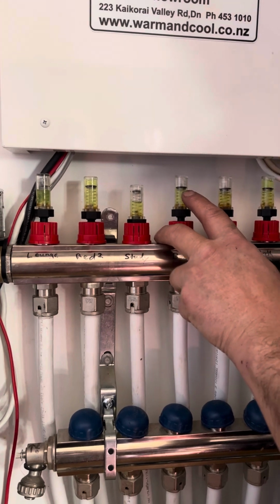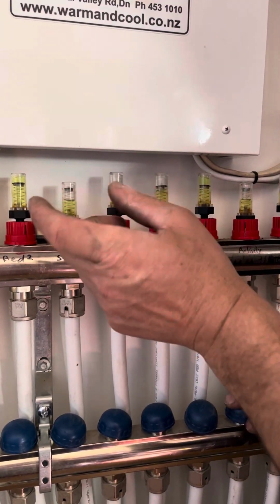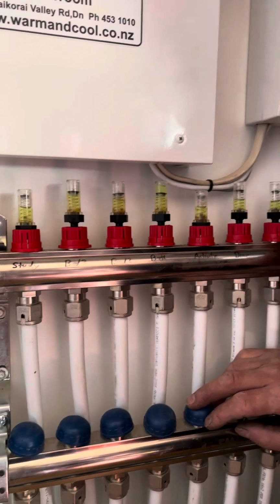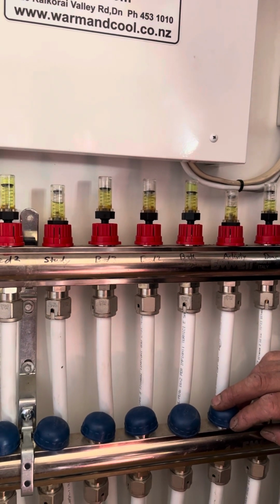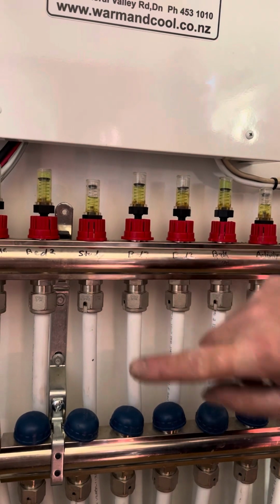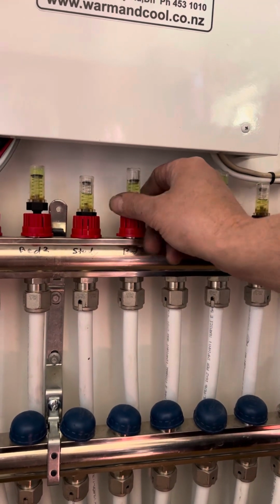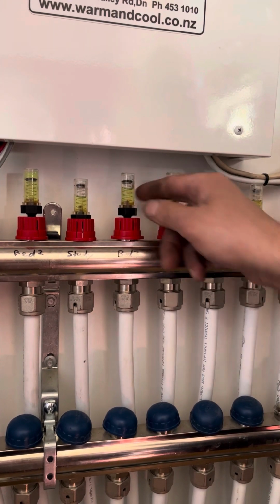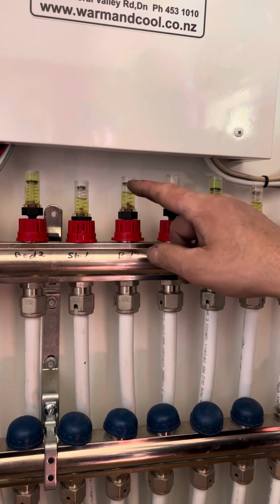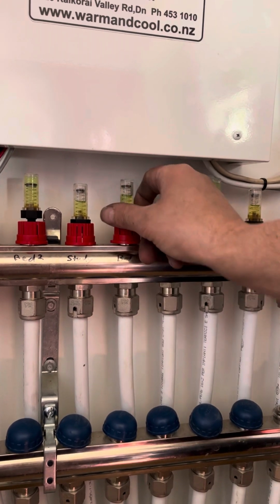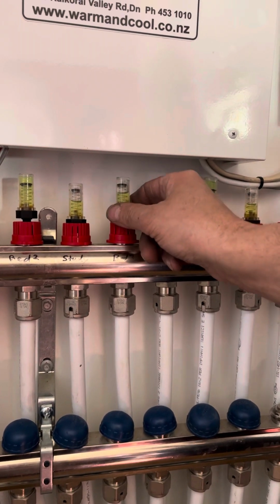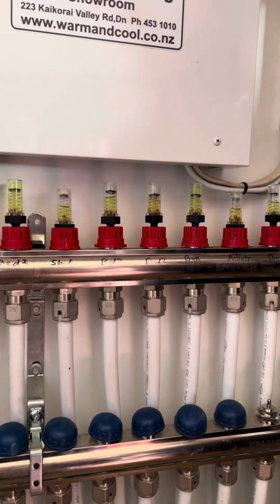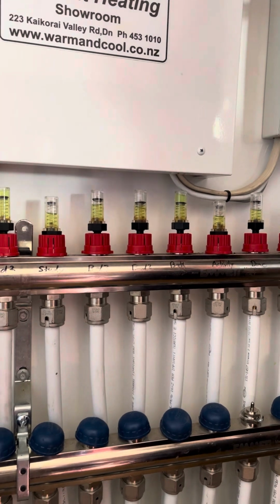So we can see we've got wee flow indicators inside the clear tubes. They're all sitting sort of 1 or 2 litres a minute, which means there is 2 litres a minute flowing through all of your zones. So if you want to reduce the heating in bedroom 3, for instance, because it's a bit warm, you can turn that one and the wee red indicator rises up higher. So if we're right up the top, then there's no water flowing through. If we screw it down a wee bit, we can now see it's 1/2 litre a minute, which is less water flow, equivalent to less heating.